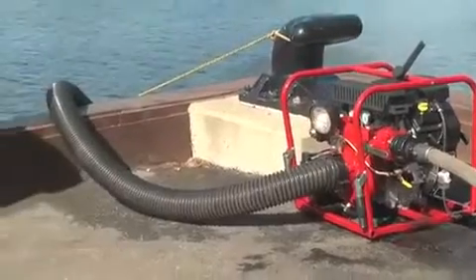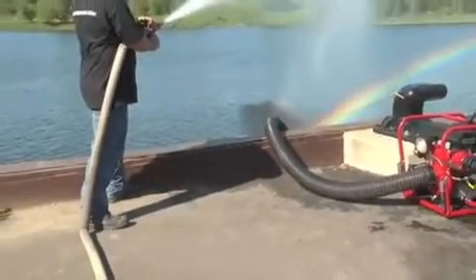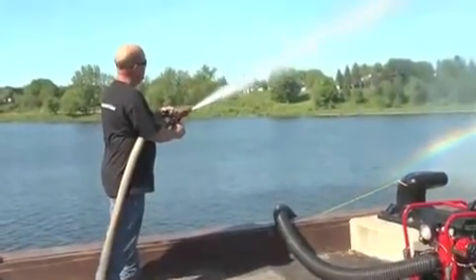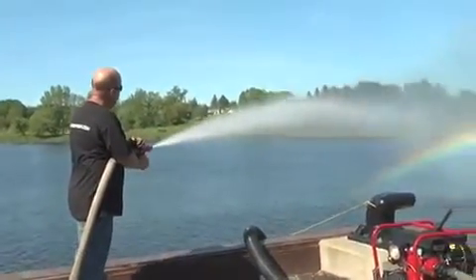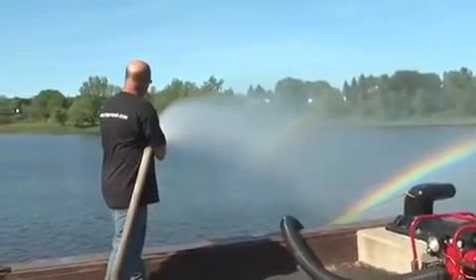Be sure to do this in the exact order to prime the pump properly. It will take approximately 30 seconds to prime the pump with one length of suction hose, and one to one and a half minutes with multiple lengths of suction hose.